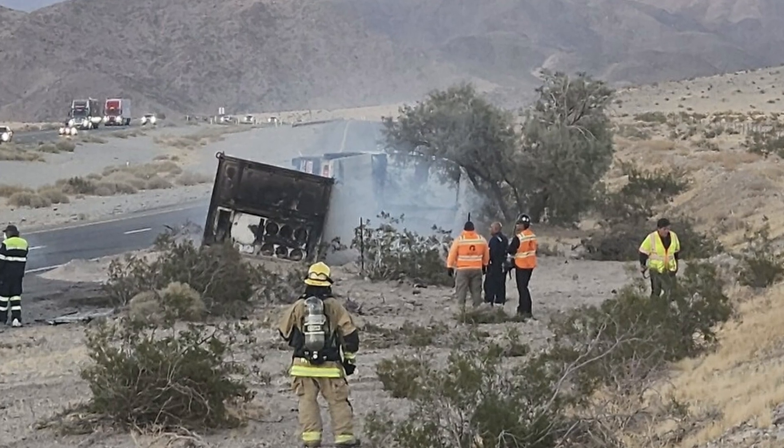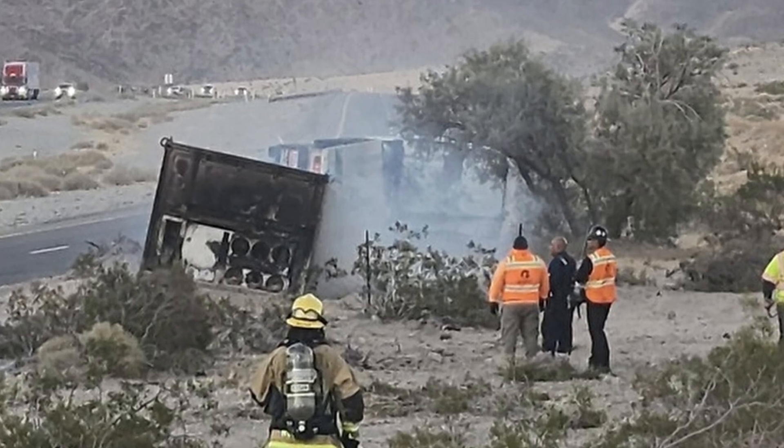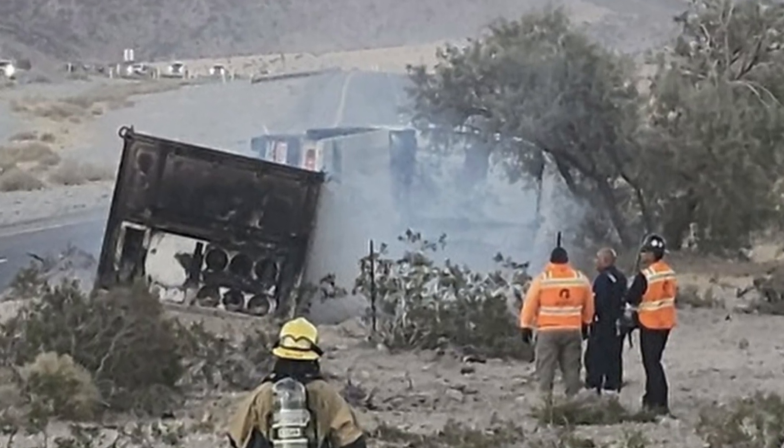These energy storage systems are designed to be on flat ground — they're not really designed to be moving around. Unlike an electric vehicle, which is designed for impact to protect the batteries, these types of systems aren't designed like that. So likely, when this unit rolled over, battery modules were knocked loose. You had mechanical damage that damaged the battery modules, caused bus bars to short out, and caused thermal runaway inside, causing those batteries to off-gas.